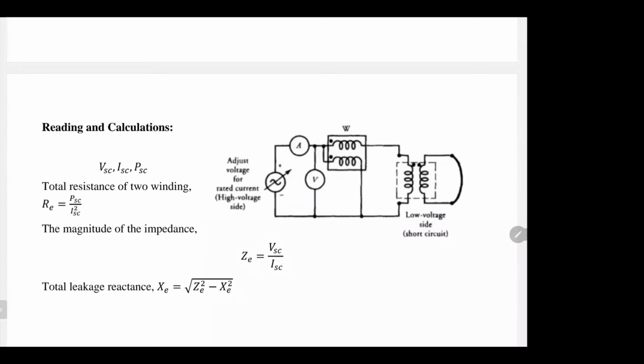So do you expect that when you put the voltage source on the high voltage side, you're going to use the rated value of the voltage? That's a common sense question. You short circuit the secondary, and you have all the measuring instruments and the power supply at the high voltage side. Are you going to apply the rated voltage of the transformer? No. Why? On either side, if you put the rated load, you get the rated current.